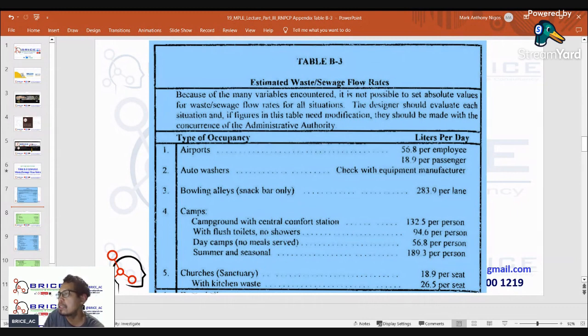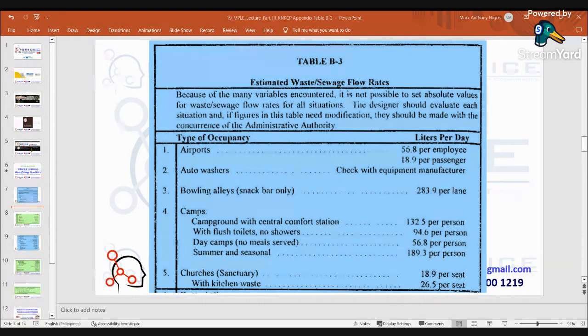Number 1: Type of occupancy — Airports: 56.8 liters per day per employee, or 18.9 liters per day per passenger. Number 2: Auto washers — check with equipment manufacturer. Number 3: Bowling alleys, snack bar only — 283.9 liters per day per lane. Number 4: Camps — campground with central comfort station: 132.5 liters per day per person.